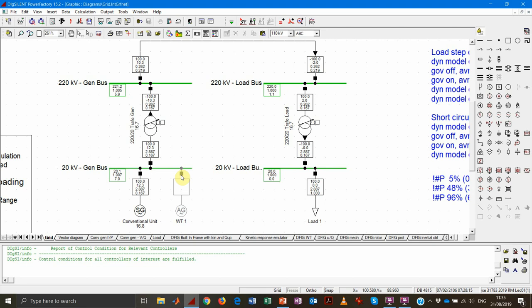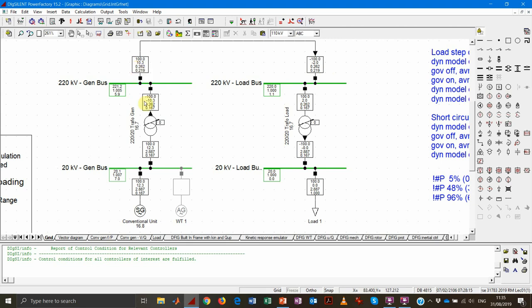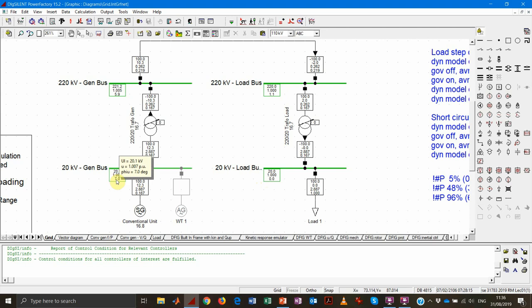We do have reactive power losses, however. The elements in the system need reactive power to get magnetized. Specifically, this transformer will be consuming a couple of MVAr — that's the power necessary to magnetize the series reactance of the transformer. The line will also consume a certain amount of reactive inductive power. Remember we are not considering any capacitive effect. The other transformer on the far end is also consuming its share of reactive power.